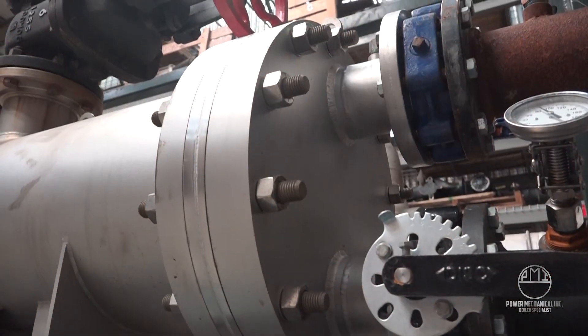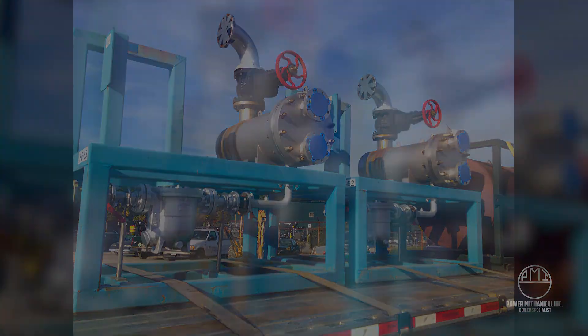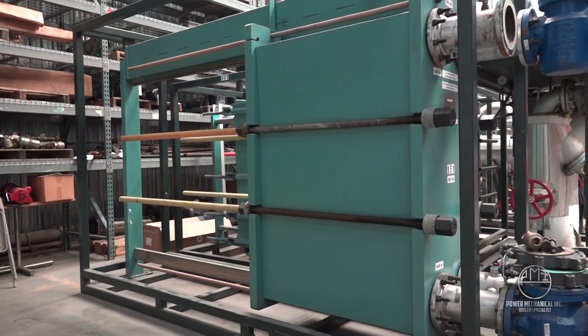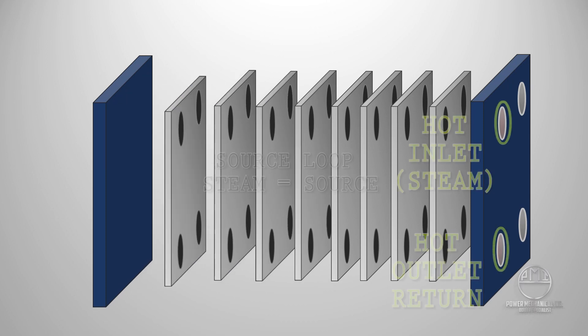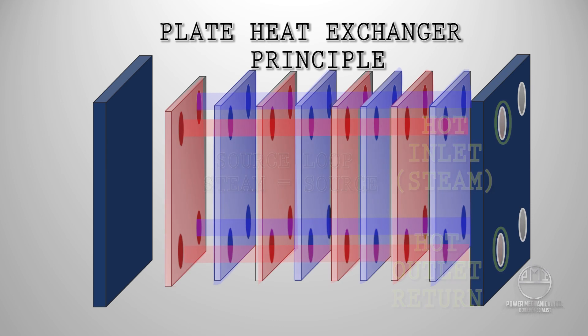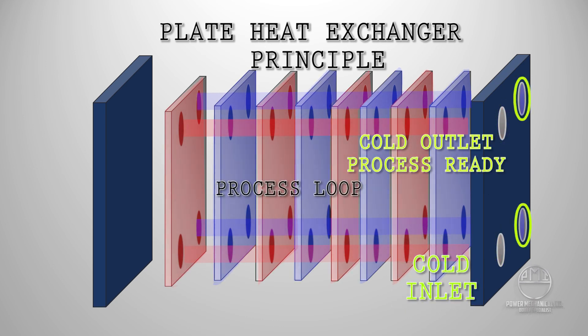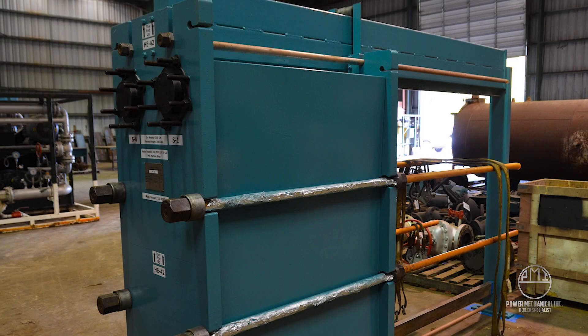Tube diameters of the bundle can limit the fluids used in the system due to risk of fouling and clogging. A plate heat exchanger offers the most efficiency and heat transfer. The design with stacked plates alternating source to process allows for greater contact between the two mediums. The thin corrugated plates create a very large surface area and make for rapid heat transfer. Their modular design makes increasing capacities possible.